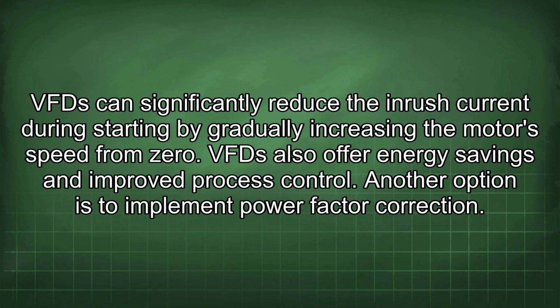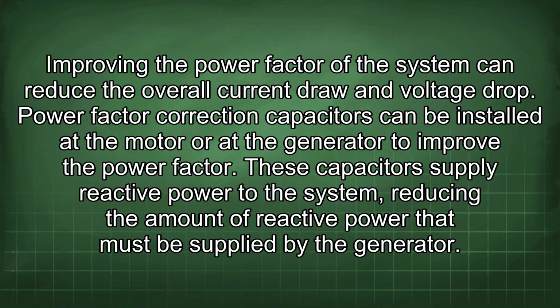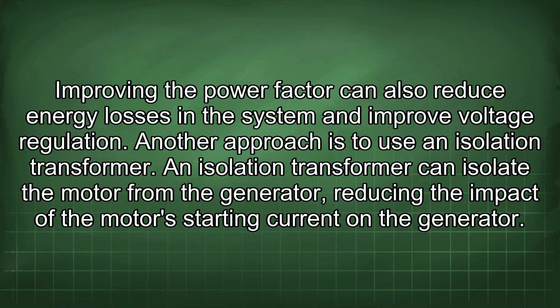Another option is to implement power factor correction. Improving the power factor of the system can reduce the overall current draw and voltage drop. Power factor correction capacitors can be installed at the motor or at the generator to improve the power factor. These capacitors supply reactive power to the system, reducing the amount of reactive power that must be supplied by the generator. Improving the power factor can also reduce energy losses in the system and improve voltage regulation.